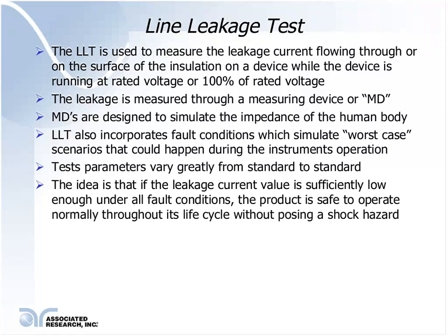Line leakage test parameters, like other test parameters, also vary greatly from one standard to another. However, some of the most commonly run line leakage tests are for compliance to the 60601-1 third edition standard, which is the medical device standard.